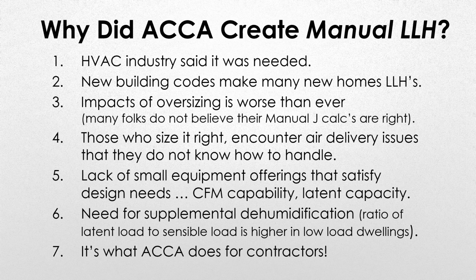So the problem is when you go to look for equipment selection, while the equipment now will handle the sensible load, it won't handle the latent load, which never used to be a problem before. But as we go to smaller equipment, because of that difference in ratio, it creates some conflict, especially in the southern market. And after all, it's what ACCA does for contractors. We try to write manuals for contractors so they can do the job right.